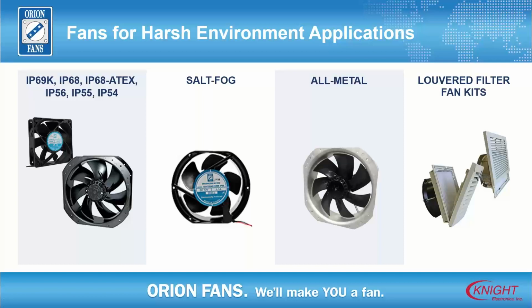Most of the really harsh environment fans are metal framed with plastic impellers. We do have metal frames with metal impellers. It's not necessarily absolute that you have to have it, but because of the environment we tend to. The frames are not going to break from water or what have you, but the metal frame gives you a little better heat transfer, and that's part of what that's all about. We can do up to IP69K, which IP69K is washed down for medical and food service. That's what it was done for.